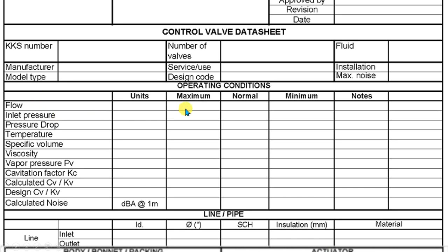Now we move on and take a close look at the operating conditions, which is super important to specify any equipment. Although for control valve sizing, we might need operation data for all three points of maximum, normal, and minimum flow rates, we usually need only maximum values for a manual or unofficial sizing. Other parameters including inlet and outlet pressures, temperature, specific volume, viscosity, and vapor pressure associated with the three operation points should be indicated. Sometimes when process engineers are sizing the valves, they don't have all this data and need to consult with the manufacturer to be able to complete these parts.